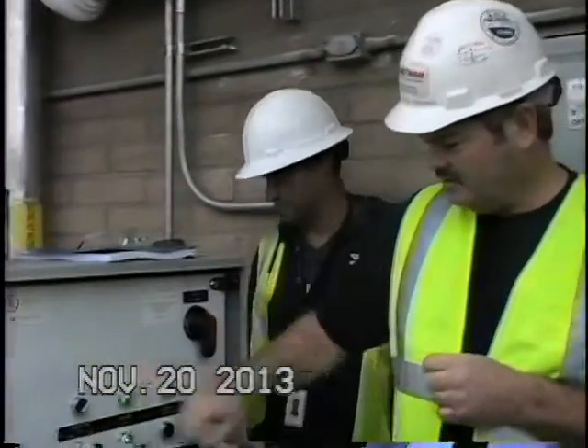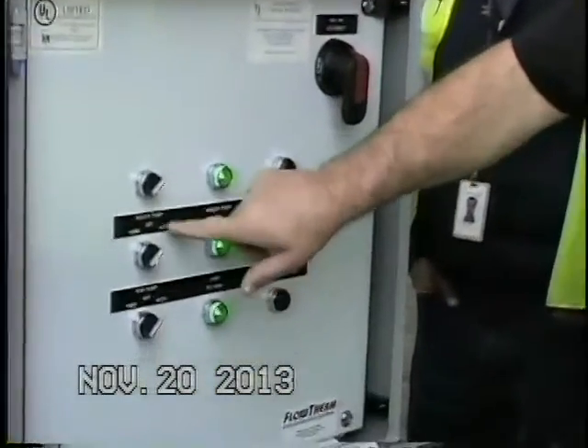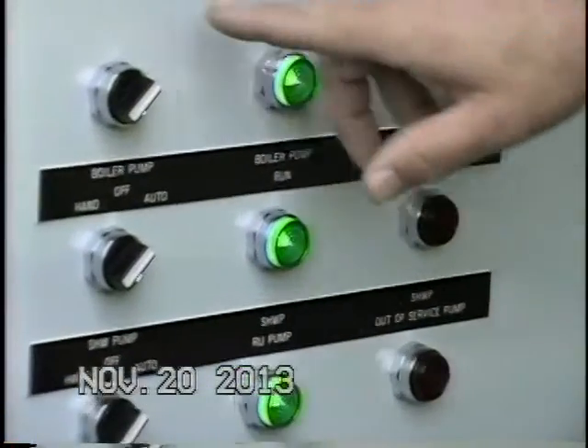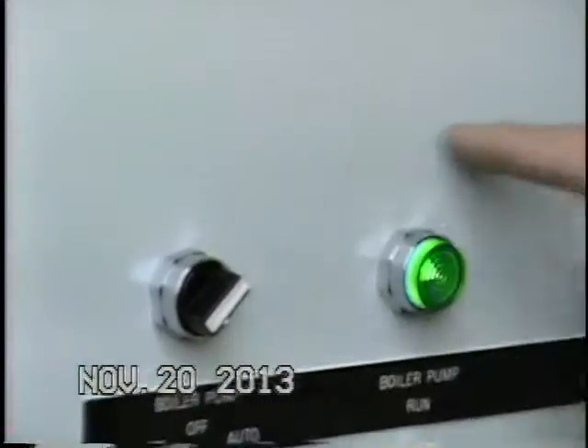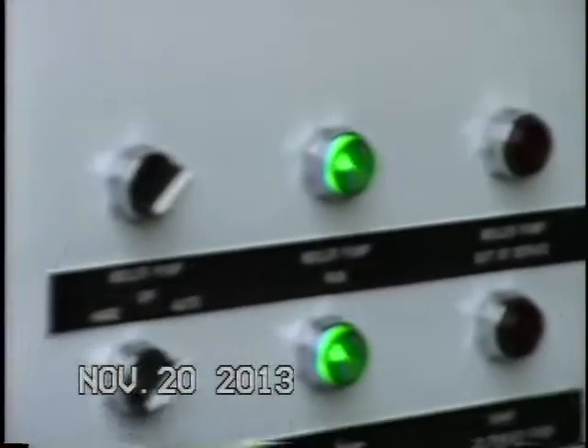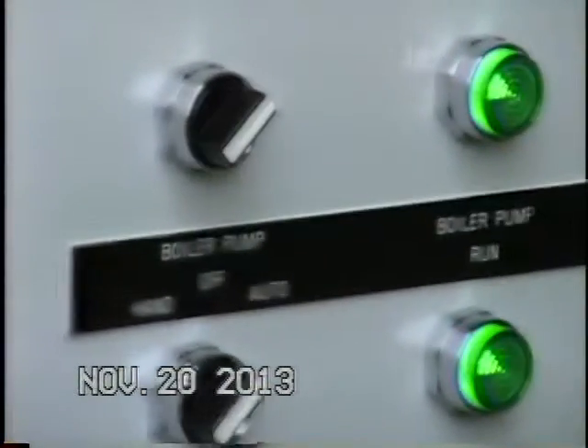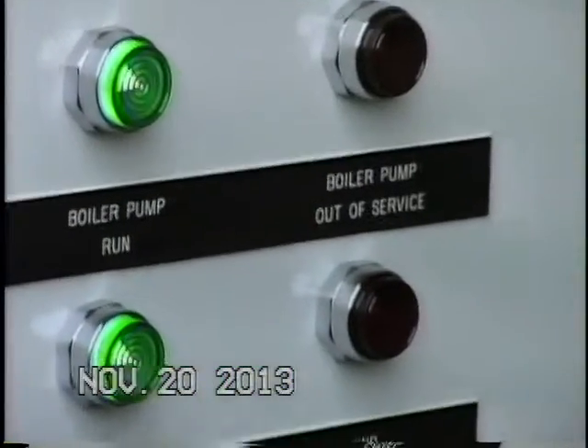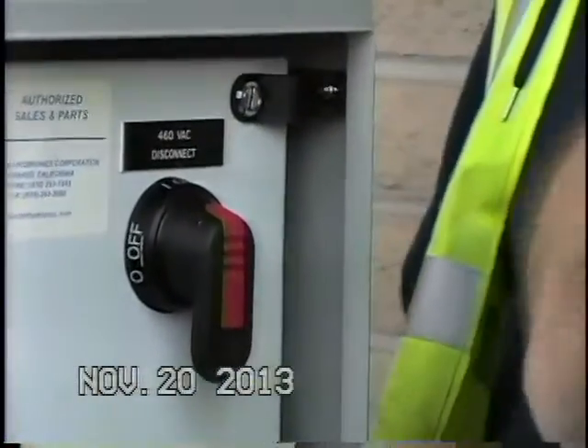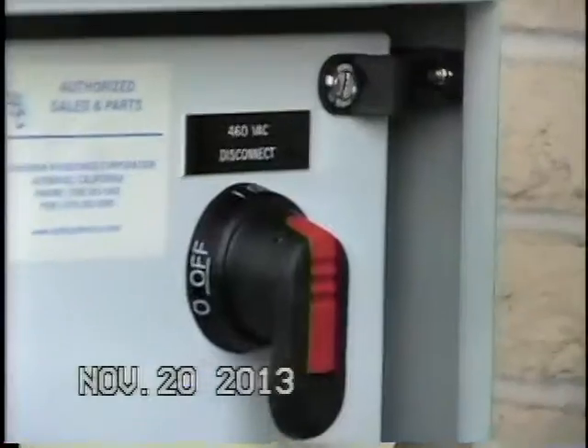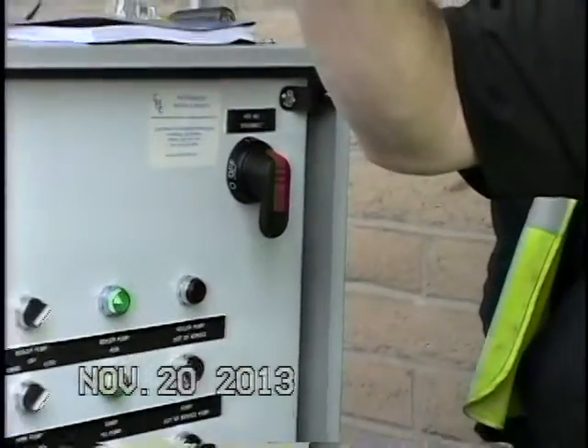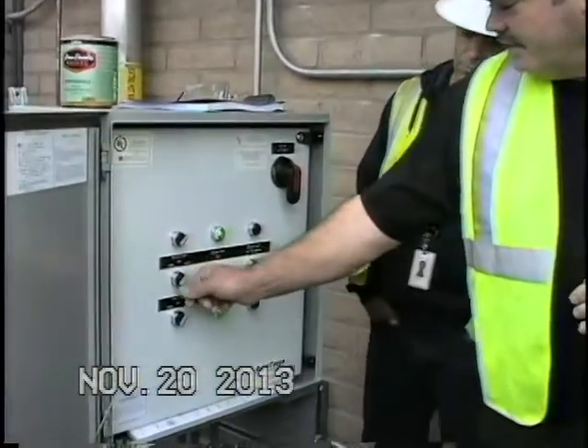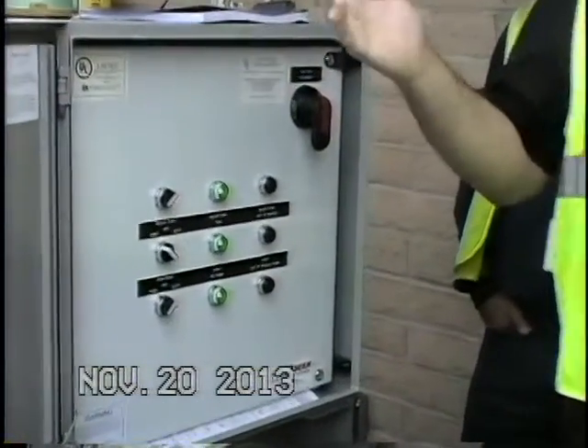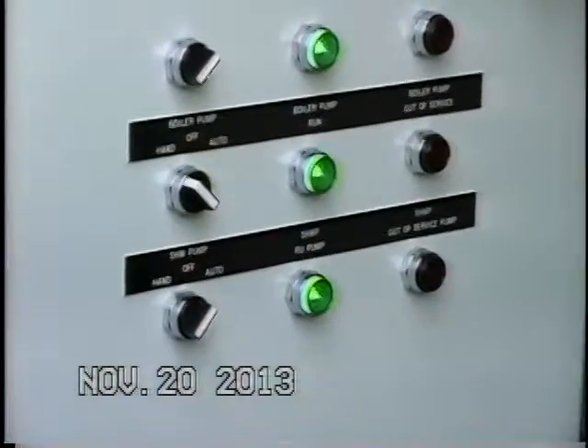Okay. Control panel. This runs the boiler pump, the system pump, and the label's falling off here, but we're going to get a new one. This is the hand-off-auto for the system. So anytime that you want to work on something, they have a box here which provides power to this. I recommend shutting this off and locking it out with a tag out lockout. But if you're having issues and it's not working like it's supposed to, you can always come over here and just turn it in hand.